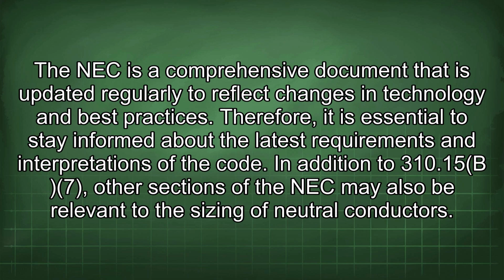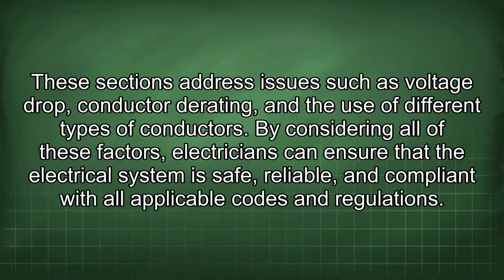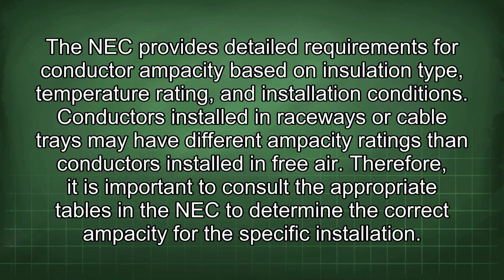In addition to 310.15(B)(7), other sections of the NEC may also be relevant to the sizing of neutral conductors. These sections address issues such as voltage drop, conductor derating, and the use of different types of conductors. By considering all of these factors, electricians can ensure that the electrical system is safe, reliable, and compliant with all applicable codes and regulations. The NEC provides detailed requirements for conductor ampacity based on insulation type, temperature rating, and installation conditions.